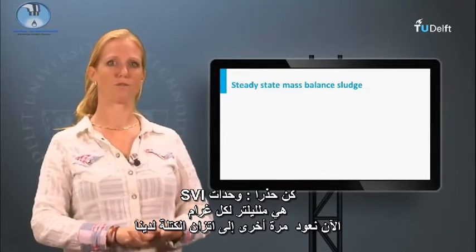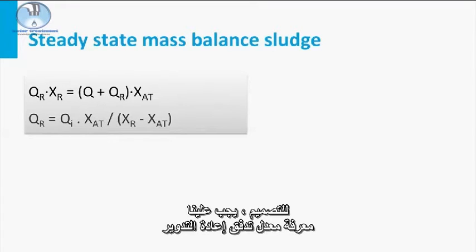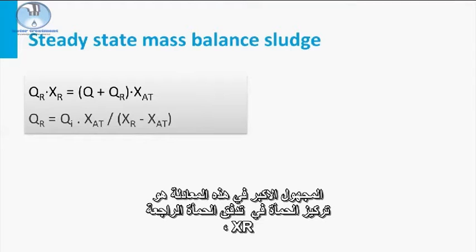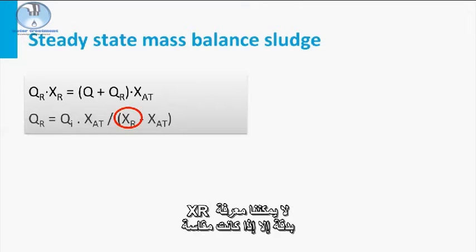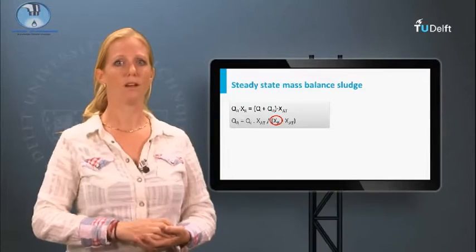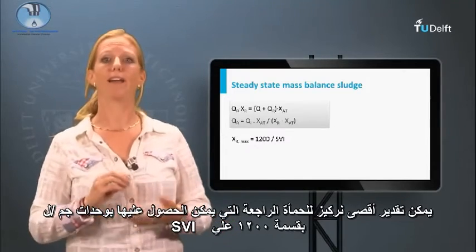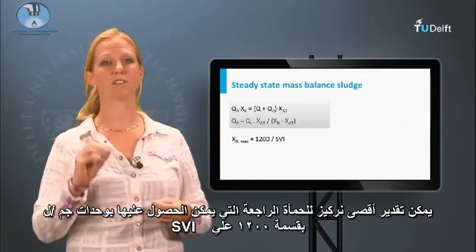Now back to our mass balance of the aeration tank. For the design, we should know the recycle flow rate. The big unknown to solve this equation is the sludge concentration of the recycle flow, Xr. We cannot know the precise Xr unless we would measure it. Often returned sludge concentrations from secondary clarifiers are between 4 and 12 grams per liter. We could estimate a maximum obtainable sludge concentration in grams per liter by dividing 1200 by the SVI.